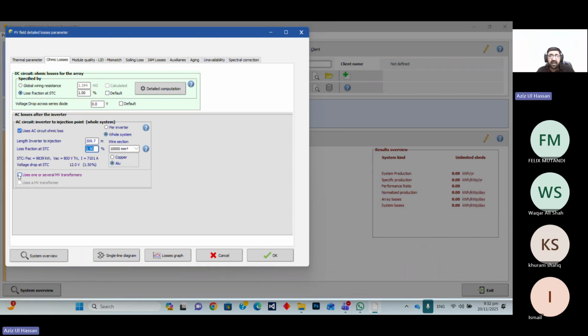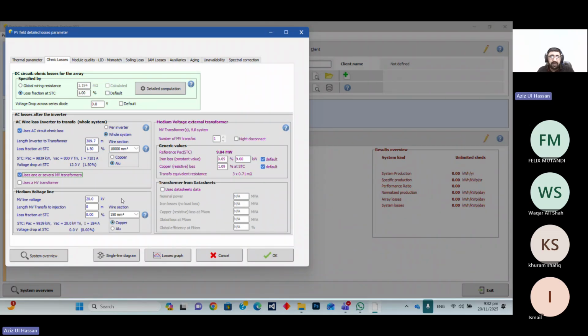So in our case, we are considering that we should include the MV and HV transformers, because with a 10 MW system we mostly assume it will be terminated at a 132 kV or 66 kV system. So we should include both these losses, for your understanding and your working. So I have clicked on that option, and it will ask me what is your medium voltage line, sorry, voltage level. We should consider it to be 33 kV.